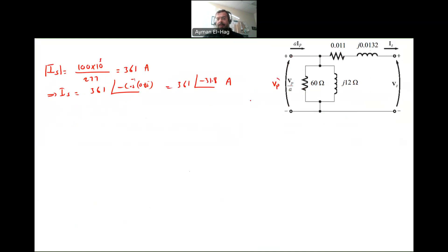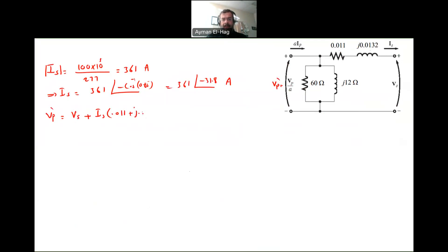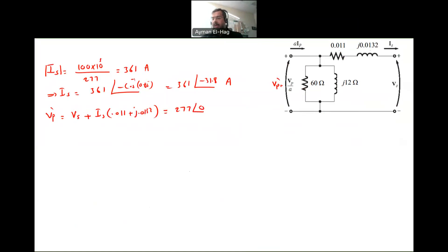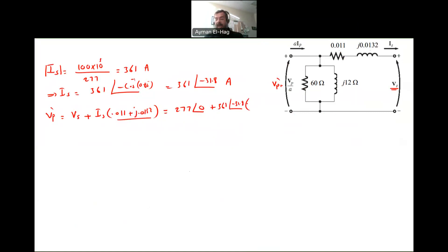VP prime equals, by simple KVL, VS plus IS times (0.011 + j0.0132). This is equal to 277 angle 0 — since the load is connected at 277 and VS is always our reference — plus the current 361 angle minus 31.8 times the series resistance and leakage reactance, 0.011 plus j0.0132. And if you do that, you will get 283 angle 0.4. So this is your input voltage.